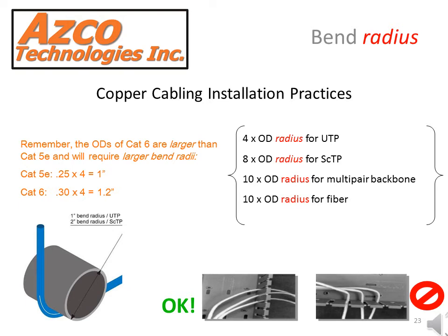As you can see, there is a proper bend radius application on the far left, and of course a misapplication on the right with a sharp 90, and a proper application in the middle of how to do it properly.